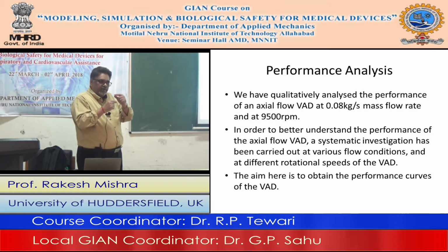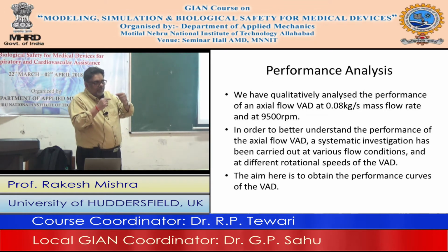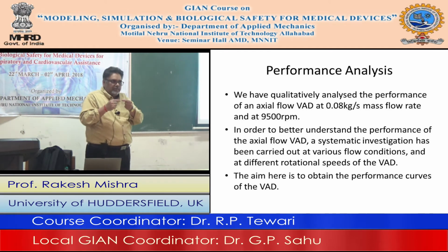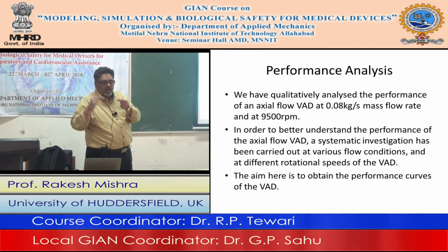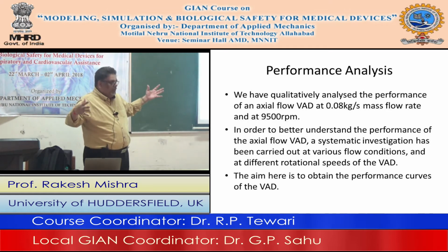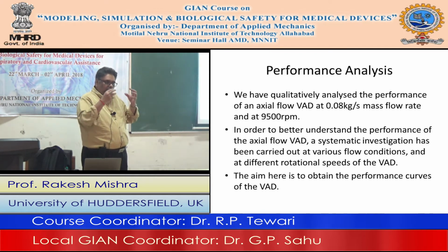blood and the ventricular assist device is happening at the local level, isn't it? The shear rate, wall shear stress, effect of rotation on the blood properties, effect of blood on the performance of the VAD will take place at the local level.